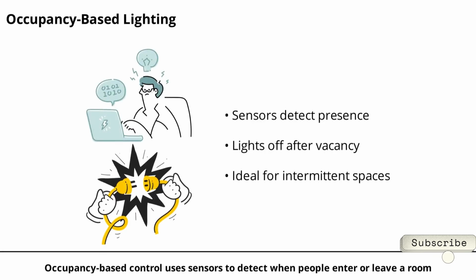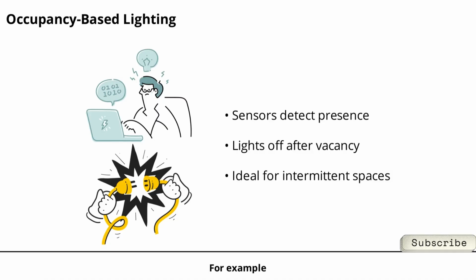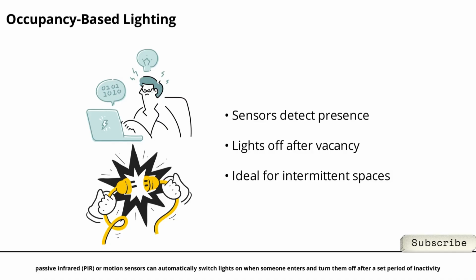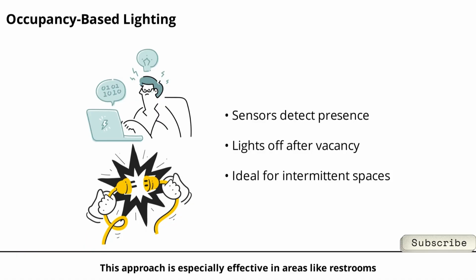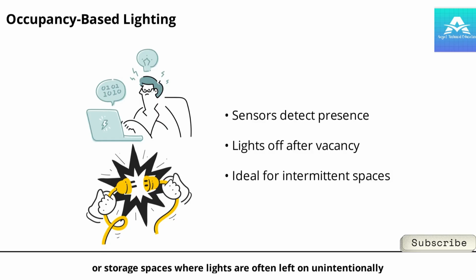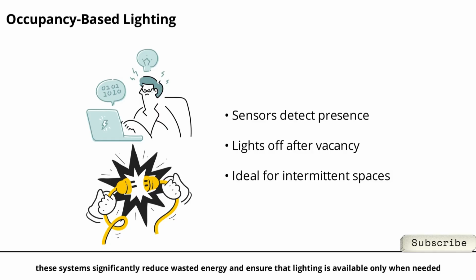Occupancy-based control uses sensors to detect when people enter or leave a room. For example, passive infrared, PIR, or motion sensors can automatically switch lights on when someone enters and turn them off after a set period of inactivity. This approach is especially effective in areas like restrooms, meeting rooms, or storage spaces where lights are often left on unintentionally. By responding to real-time occupancy, these systems significantly reduce wasted energy and ensure that lighting is available only when needed.